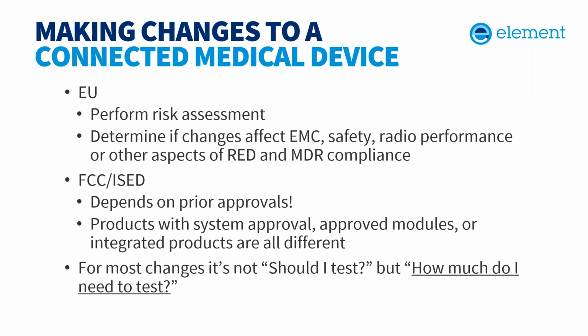For the EU, if there are changes to the radio circuit, it depends on how the radio was previously approved. If you had to do a type examination certificate, you might have to do one again. And you may only need to do spurious emissions for testing, but again, it depends on the change. Then any immunity testing under the RED is going to be determined by your risk assessment.